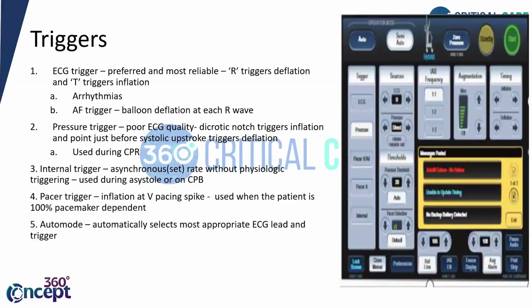Next, coming to the internal trigger. So it is an asynchronous set rate. It is like a default rate which is already set without any physiological triggering. It is mainly used when your patient is not giving any ECG activity or there is no arterial trace. So like when you're on a cardiopulmonary bypass pump, you see we don't have a proper arterial trace. So that is when you will use this internal trigger, when you don't have a good ECG or an arterial pressure waveform.